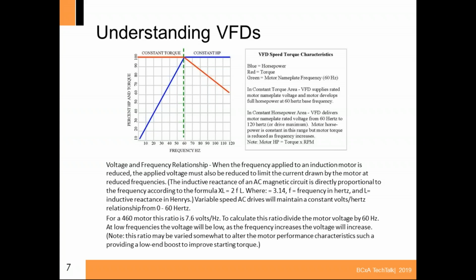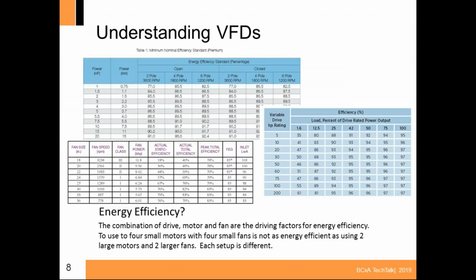But we'll go on. Now this is where, to me, it gets a little tricky with VFDs and direct drives. I said earlier that this stuff is really energy efficient. Well, you can see this is the energy efficiency standard, the top one, the minimum for standard premium. As you can see, a 4-pole motor, which is a nominal 1800 RPM motor, is probably the most efficient motor made. But in this case, a 1 horsepower motor is not as efficient as a 4 horsepower motor by quite a bit.